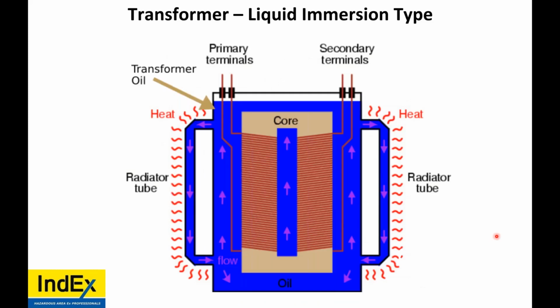So what is the purpose of the oil in a liquid immersion type? It absorbs the heat produced by the internal components of the core of the transformer. That allows the heat to radiate through the body equally, so that it does not become so much that it could ignite a potentially hazardous atmosphere outside. So it is absorbing all the heat.